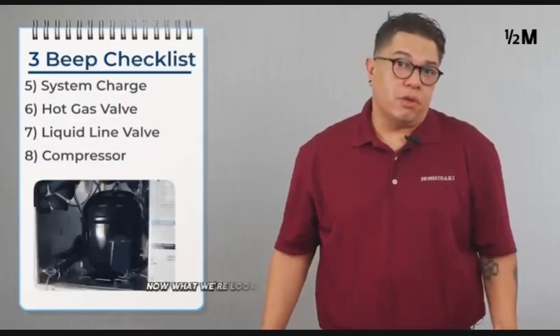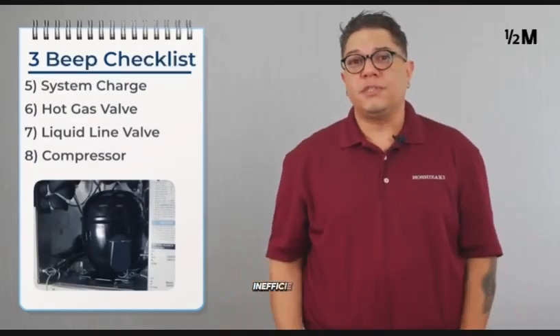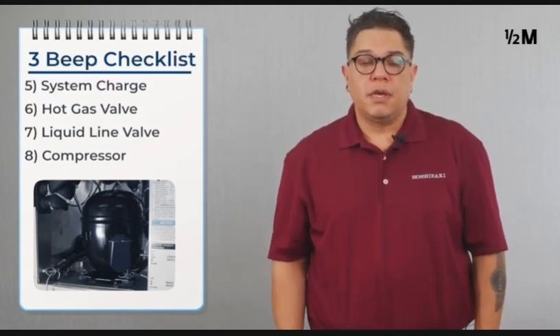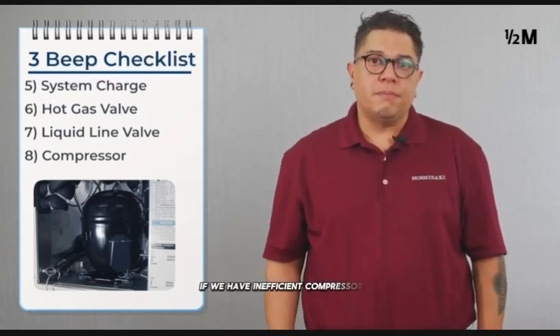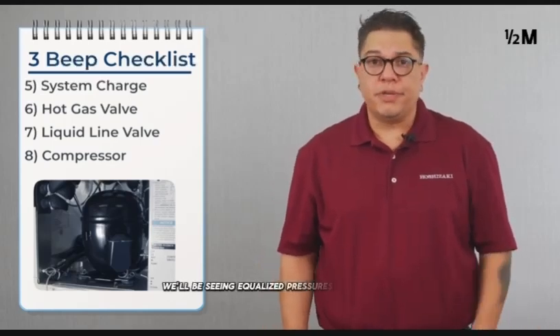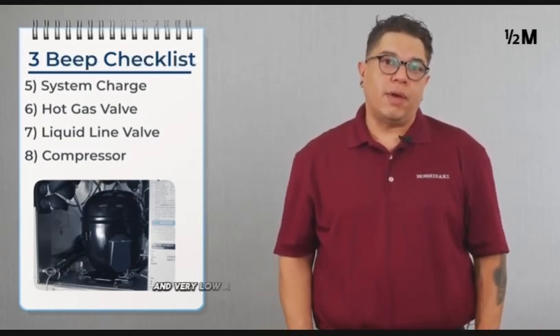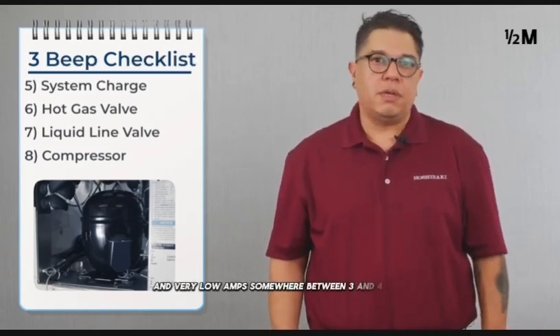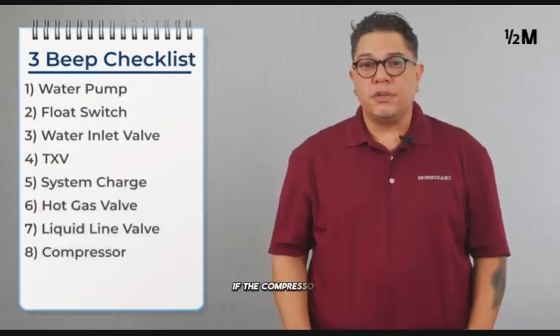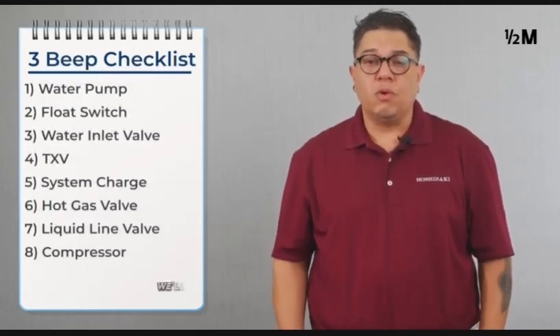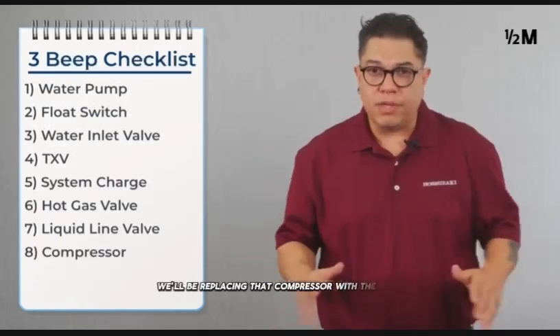Once we confirm that the liquid line valve is working properly, now we can move over to the compressor. Now what we're looking for on the compressor is inefficiency, broken valves. If we have an inefficient compressor, we'll be seeing equalized pressures on both sides and very low amps, somewhere between 3 and 4 amps. If the compressor is inefficient, we'll be replacing that compressor with the dryer.